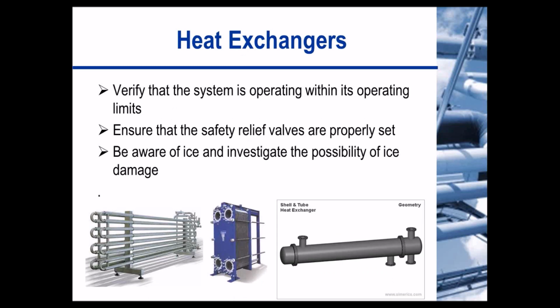Now, for heat exchangers, you want to verify that the system's operating within its limits. Ensure the safety relief valves are properly set, and be aware of ice around your system, especially ice where you're not used to having seen it before. Because as that water freezes, the expansion can cause damage to your system.